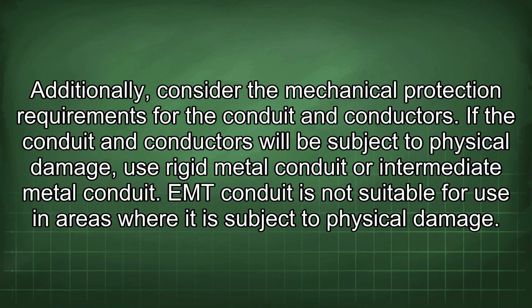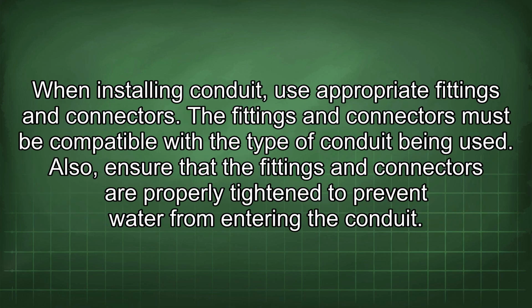If the conduit and conductors will be subject to physical damage, use rigid metal conduit or intermediate metal conduit. EMT conduit is not suitable for use in areas where it is subject to physical damage. When installing conduit, use appropriate fittings and connectors. The fittings and connectors must be compatible with the type of conduit being used. Also, ensure that the fittings and connectors are properly tightened to prevent water from entering the conduit.